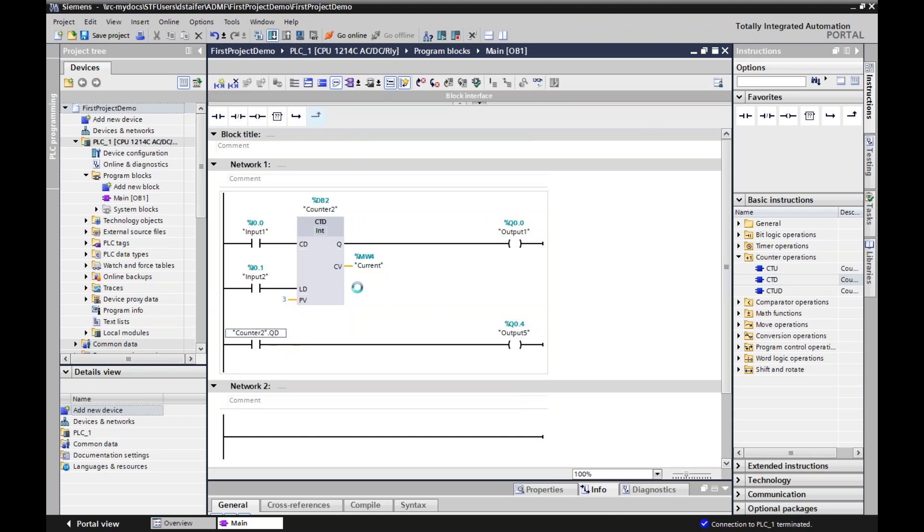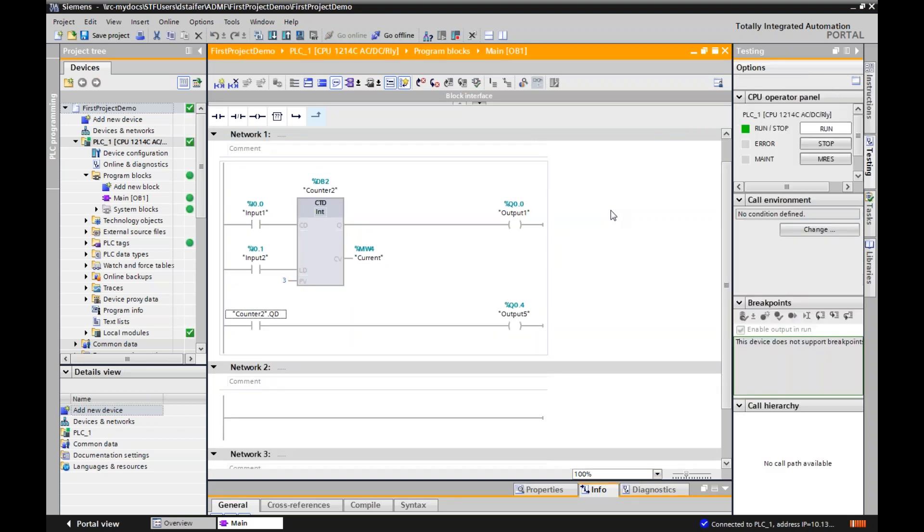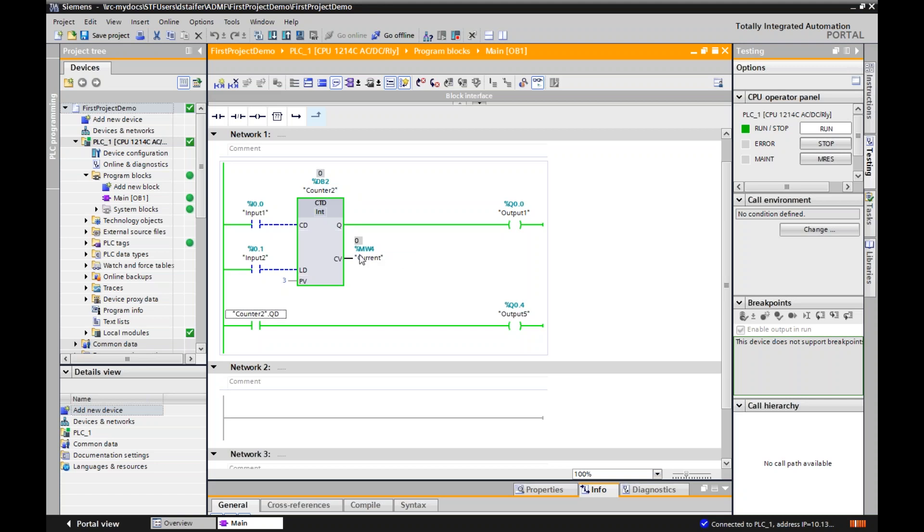So let's see this in action. Now one quick thing, I'm going to change this here to QTD, because I'm looking for the QTD, not the QTU, because I'm counting down, not up. So let me download. And let me go live. Huh. Why is my lights on? It wasn't on in my counter up. I don't understand. Well, that's because, what did I say? The Q here on a countdown goes true when the current value of the counter equals zero.